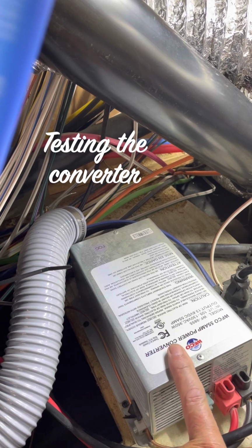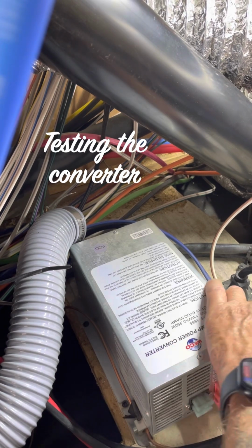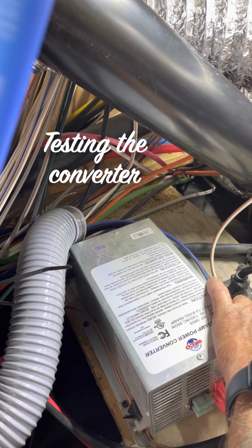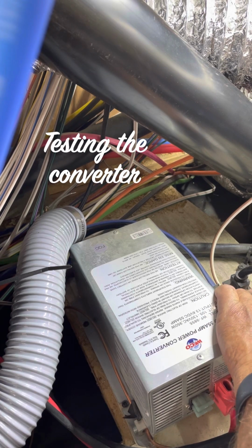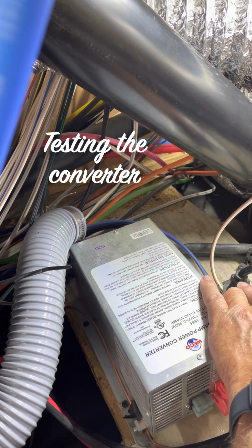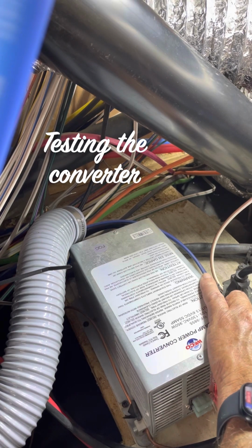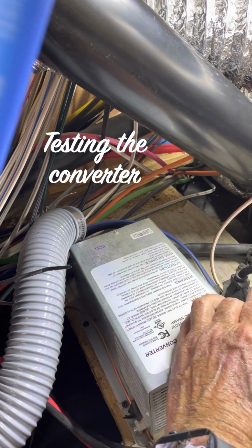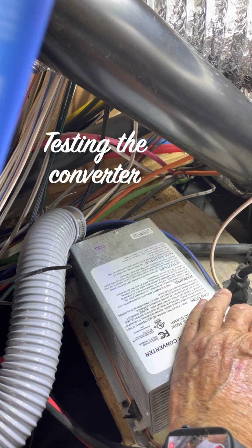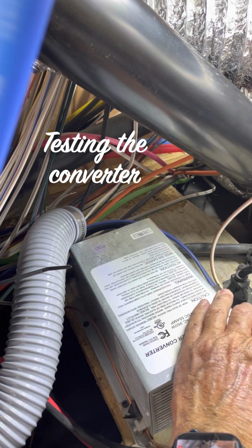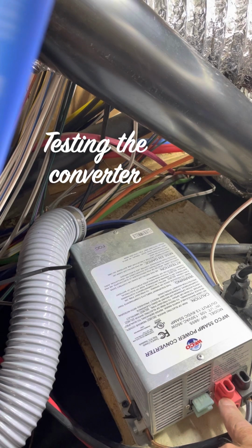Is the fan running? If it is, you have power at this outlet. If not, unplug the converter and check power at the outlet. If there's no power, then there's a wiring problem between the circuit breaker and the outlet because you have tested the circuit breaker. Check the voltage here at the output of the converter. Should be the same as what you are seeing at the batteries. If not, you have a wiring problem between the converter and the batteries.